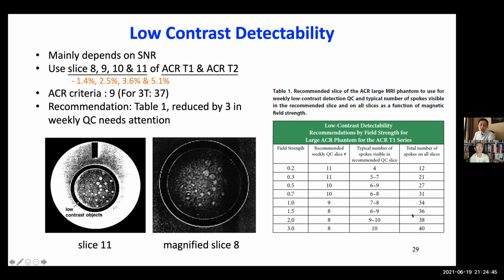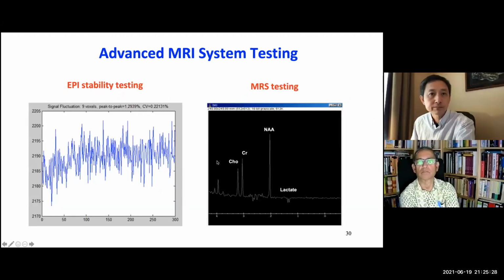Here also shows some typical scores, the recommended scores at different field strengths. For example, the 1.5T scanner is very common. The minimum for 1.5T is 9, but that's too easy to achieve, so the recommended score is actually 36. This is also scored weekly. If in any given week the score is reduced by 3, then we need to pay attention to the system. The test needs to be repeated, or we need to investigate the reason.